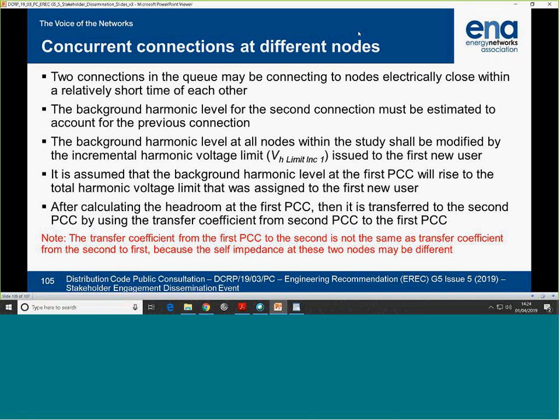Then, use transfer coefficients. We calculate the impact of the connection on remote nodes using incremental limit. Then calculate the new headroom at all those nodes. Transfer them to the new PCC, or second PCC, and apportion. So it's one step more than before. It sounds complicated, but it's really not.